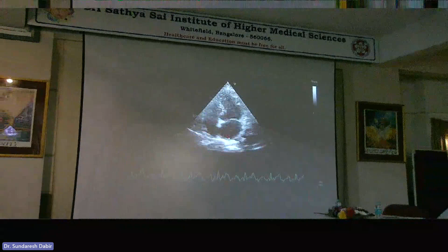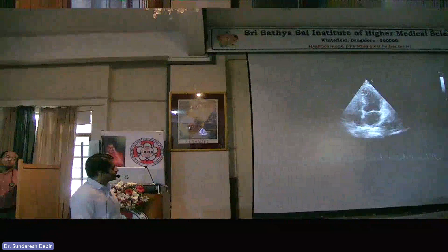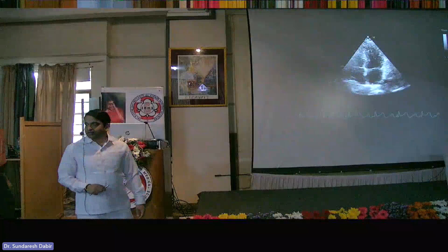Now, let's go back to this case. This is a new machine, so this doesn't have something called a focus. What does the focus do? Any idea? We talked about spatial resolution, right? So transducer frequency is one of the most important determinants of spatial resolution. In spatial resolution, you have something called axial resolution. Axial resolution means in the same line, what's your ability to distinguish two separate objects? Then you have lateral resolution. Lateral resolution means in the same arc, what's my ability to see two images that are lying side by side? Where I have my focus, usually shown as a line, is where I will have the best lateral resolution.